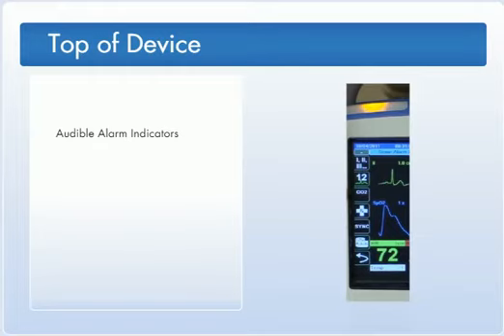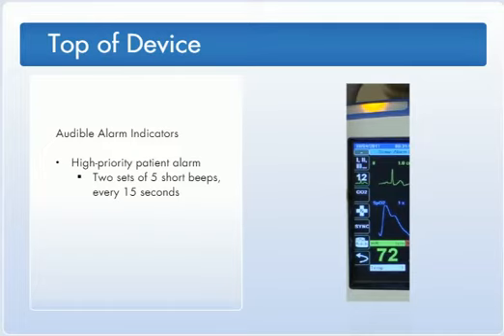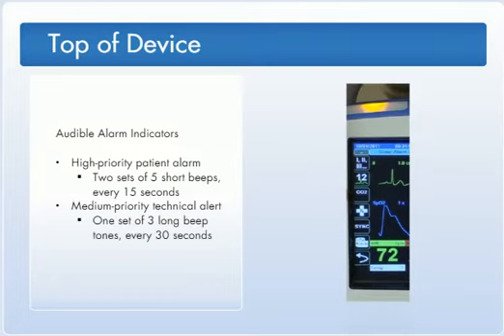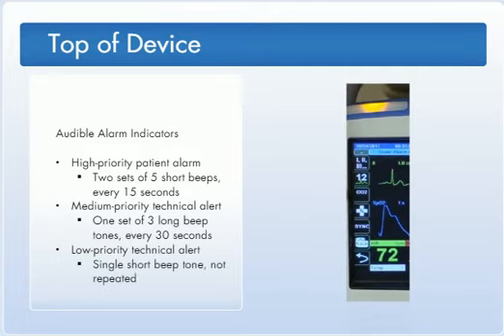The X-Series unit sounds an audible alarm to indicate the priority level of the highest priority active alarm. The X-Series indicates the priority level using a high priority alarm, which consists of 2 sets of 5 short beeps every 15 seconds, a medium priority technical alert, which is 1 set of 3 long beep tones every 30 seconds, and a low priority technical alert, which is a single short beep tone, not repeated.